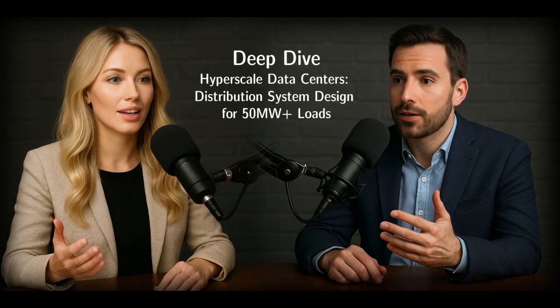We've really focused on voltage selection, and clearly it's vital. But you mentioned earlier, even with the right voltage, these data centers bring other challenges. Protection was one. How is protecting these massive electronically dense loads different from protecting a typical industrial park or residential area? It's a whole different ballgame. Traditional distribution protection relies on relatively simple time-current coordination. Basically, fuses blow and breakers trip based on how much current flows for how long. Communication between devices is often limited, and clearing times of, say, 5 to 8 cycles might be perfectly acceptable.